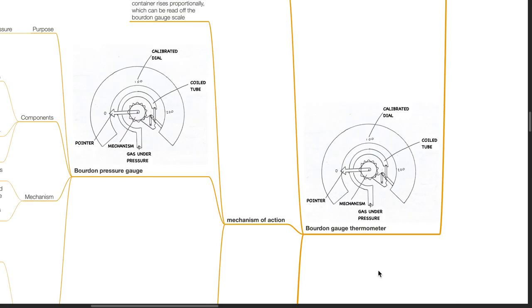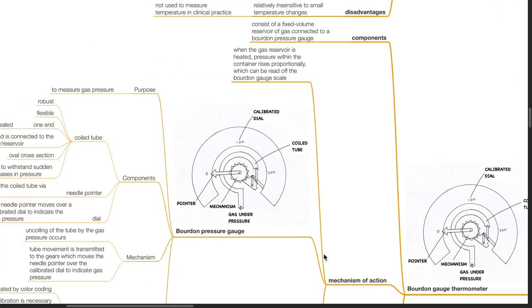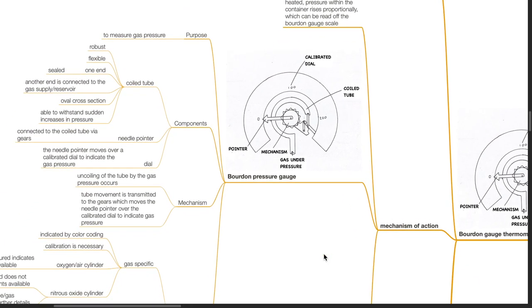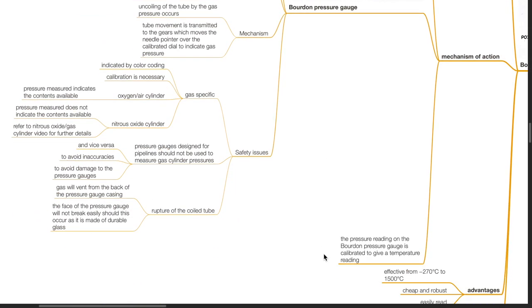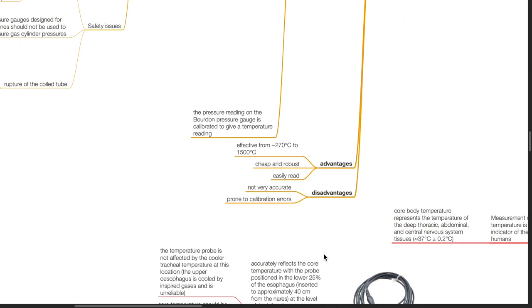Bourdon gauge thermometer: components consist of a fixed volume reservoir of gas connected to a Bourdon pressure gauge. When the gas reservoir is heated, pressure within the container rises proportionally, which can be read off the Bourdon gauge scale. For the mechanism of action of the Bourdon pressure gauge, refer to the video on the anesthetic machine. The pressure reading on the Bourdon pressure gauge is calibrated to give a temperature reading. Advantages: effective from negative 270 to 1,500 degrees Celsius; cheap, robust and easily read. Disadvantages: not very accurate and prone to calibration errors.